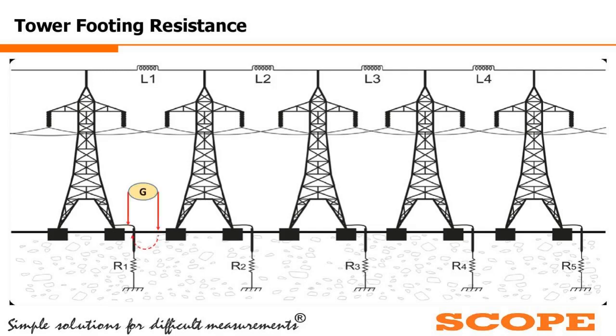The moment I put a generator or the test kit, and put the prongs as shown by the red arrows, I am supposed to get the current limited only to that zone. But practically that is not happening. It is creating a parallel path, because at the top, as we can see, there are the inductances of the line, L1, L2, L3, L4. All those things come in because the guard wire is connected into the transmission line, and we cannot remove the guard wire for the purpose of testing the tower footing resistance. So it is creating a parallel path between the first tower and the second tower.